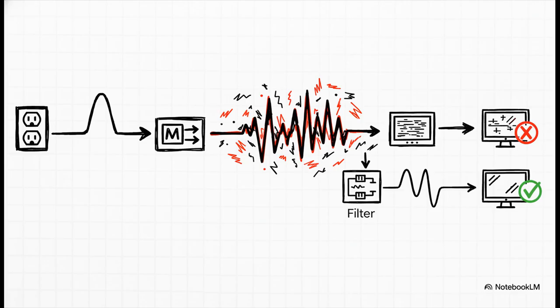But there's always a catch, isn't there? With VFDs, that complex AC to DC to AC switching process isn't perfectly clean. It can create electrical noise, what we call harmonic distortion, and push it back into the power grid. That can sometimes mess with other sensitive equipment, which might mean you have to buy extra filters, adding to the cost and complexity of the whole thing.